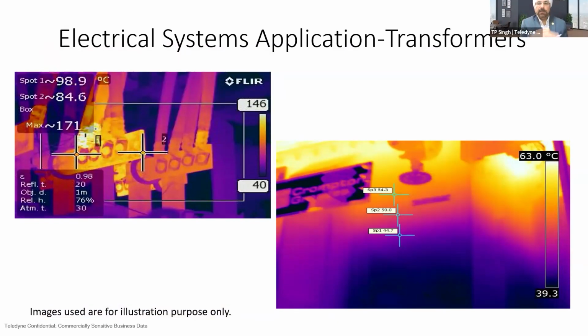Once you detect that, then you can go for vibration analysis or even DGA if that is needed. Otherwise, for both vibration and DGA you will be needing a shutdown, but for the thermal imaging camera that shutdown is not needed. So it can be treated as the first information report.